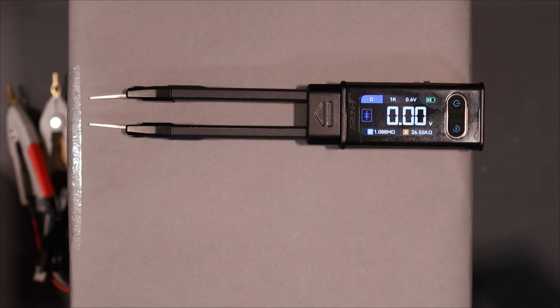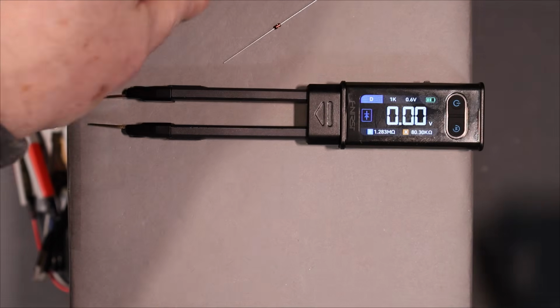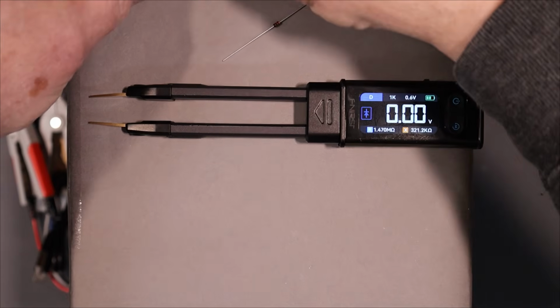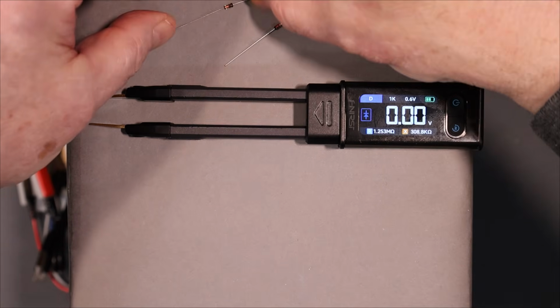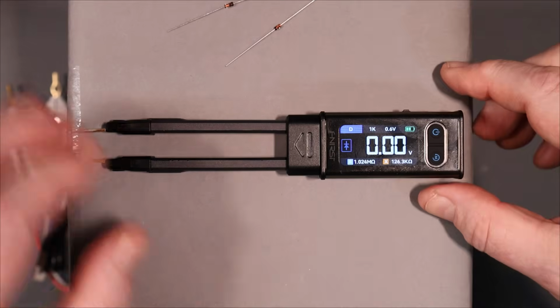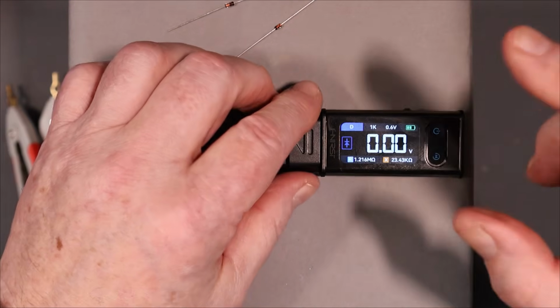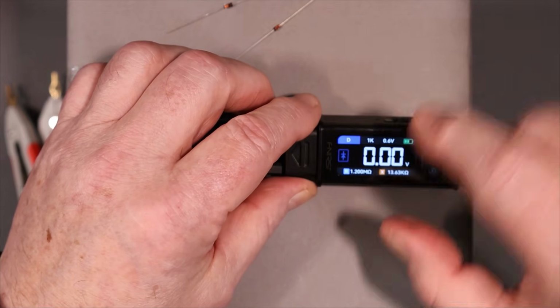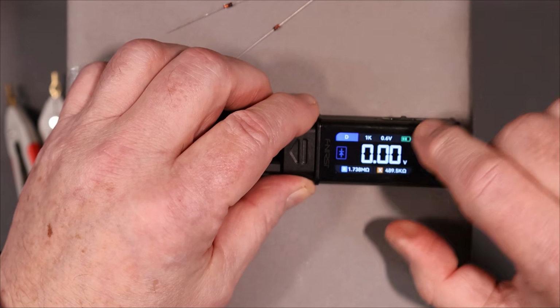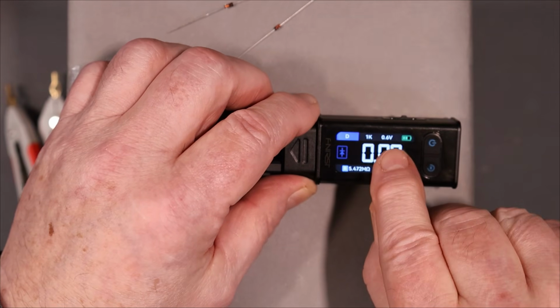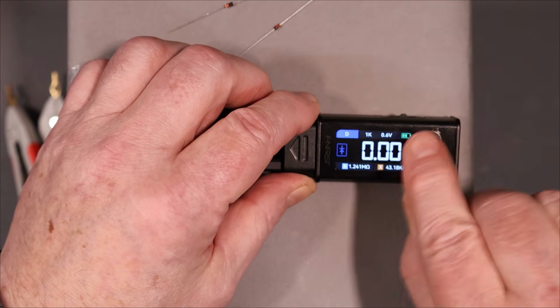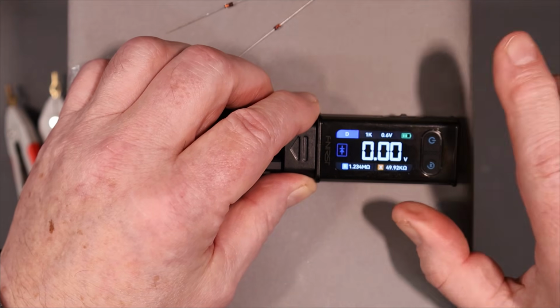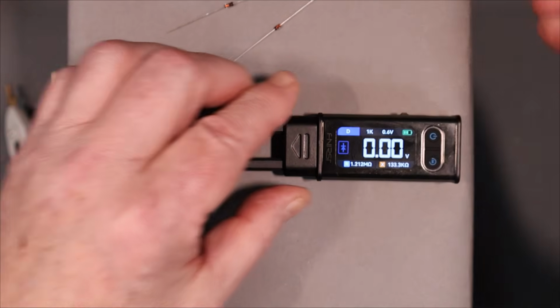Okay, we're going to check out a couple of diodes. I've got these two diodes here. One is a Schottky and one is a silicon. I wonder if we could tell which. Now, it's in diode mode, but in diode mode, I will note that you cannot change the frequency or the voltage. So you're stuck with a 0.6 volt output, which means you're not going to be able to check out LEDs with this. It's strictly for signal diodes.